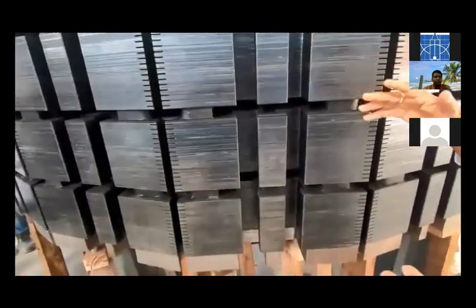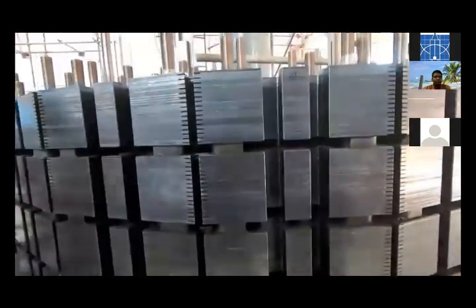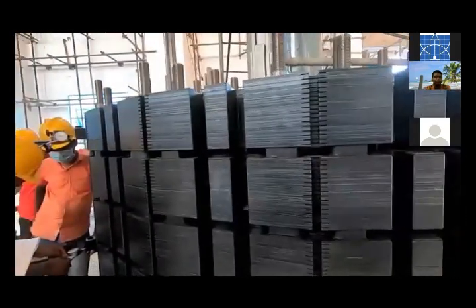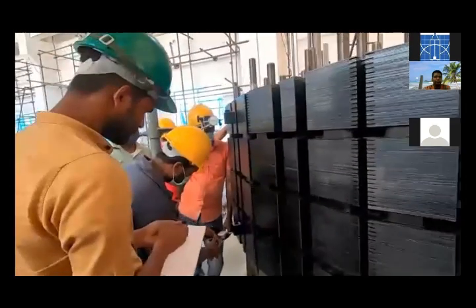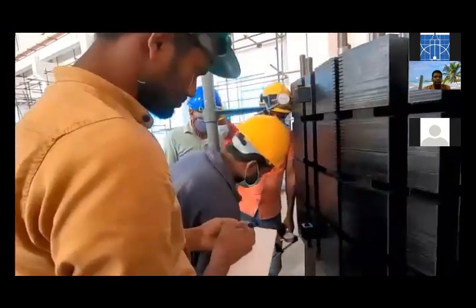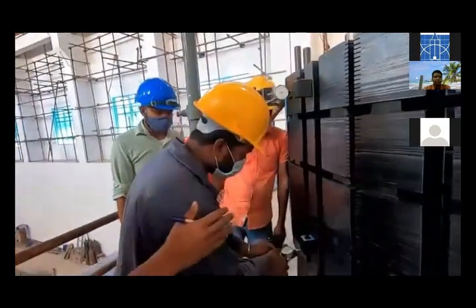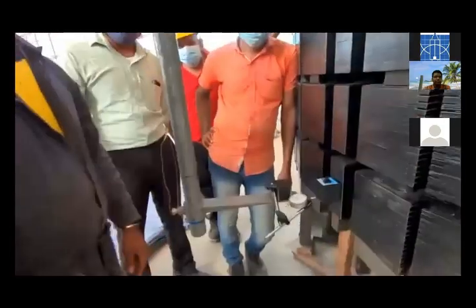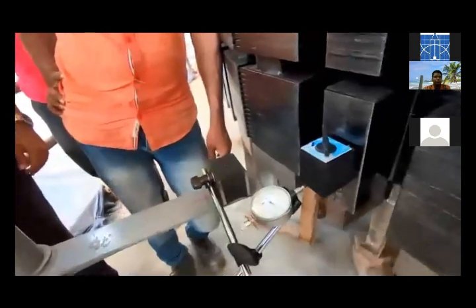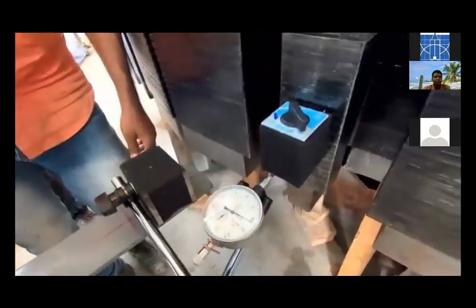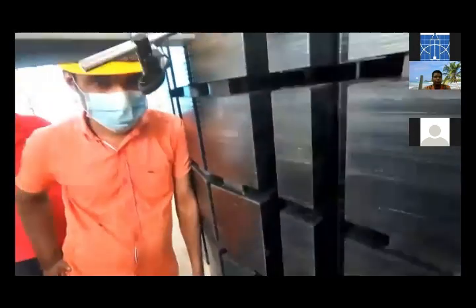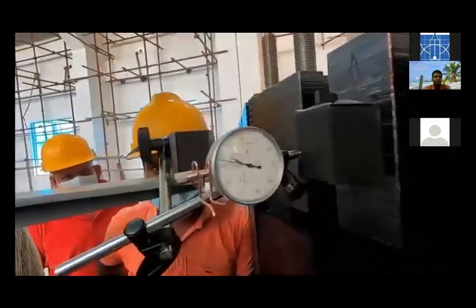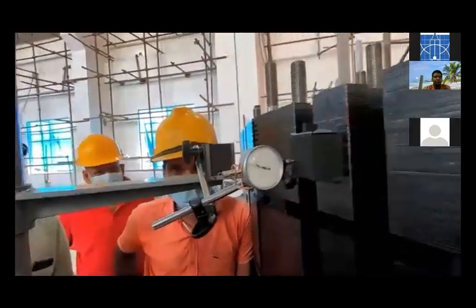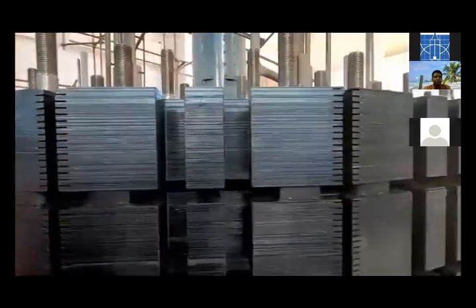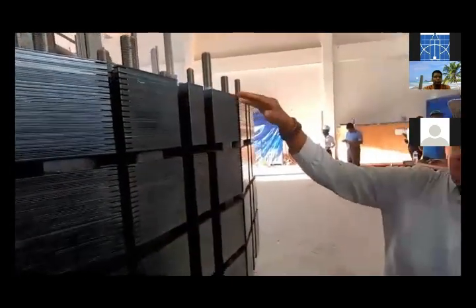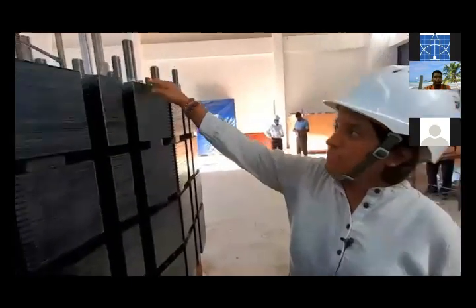After the installation, our contractor, consultant and CEB staff take some measurements to check whether they are within tolerances. This arrangement is to check the roundness of the rotor. Other than roundness, we take measurements of the diameter and the waviness of the rotor surface.